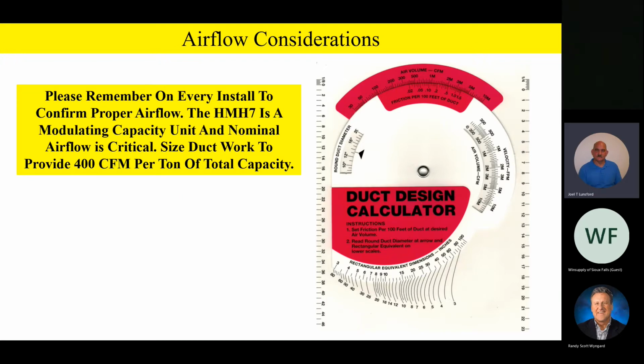We're going to ask that you make sure and size your duct for 400 CFM per ton of total cooling capacity. Again, some examples I used earlier in our program today. If you have a 2-ton unit outside, you want to make sure that your ductwork is sized for 800 CFM. If you have a 3-ton unit sitting outside, you need to size it for 1200 CFM. If it's a 4-ton unit, you're going to size it for 1600 CFM, and so on. So let's make sure that we have the proper airflow on these units.